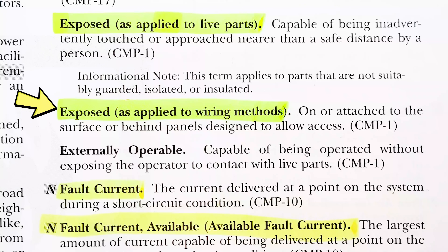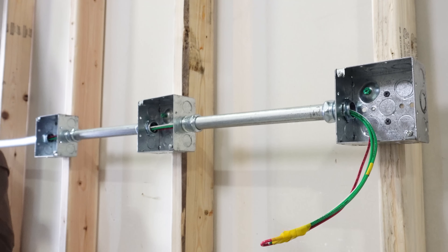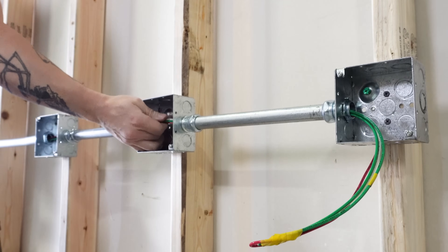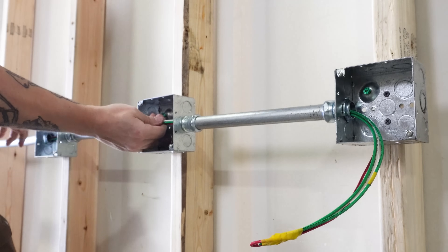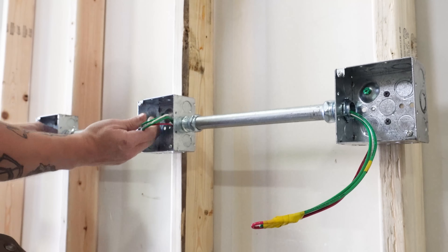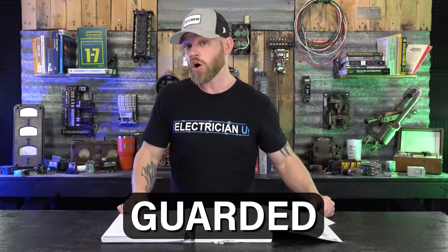Then we have 'exposed' a second time, but this one is applied to wiring methods. Here, exposed means on or attached to the surface, or behind panels designed to allow access. So if you run EMT on the outside of a wall, that work is considered exposed work.